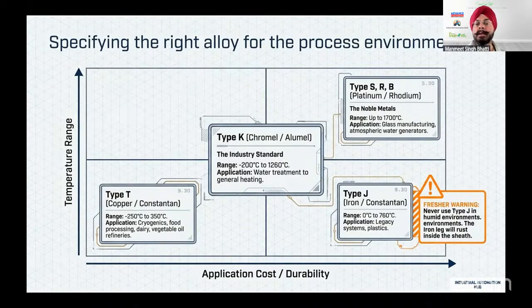Moving further to other types, S, R, and B are basically for your heavy furnace applications. They are used at temperatures up to 1700 degrees, where you can get molten material. That's why we use platinum and rhodium for that. These are very noble metals and they are very costly also. So for applications where temperatures may run up to 1700 degrees, these classifications of thermocouples are used. Then we have another, which is called type J.